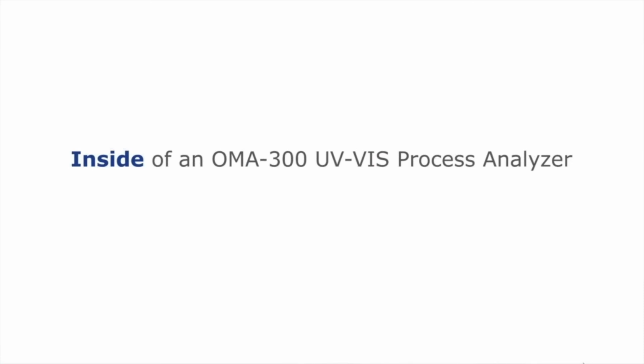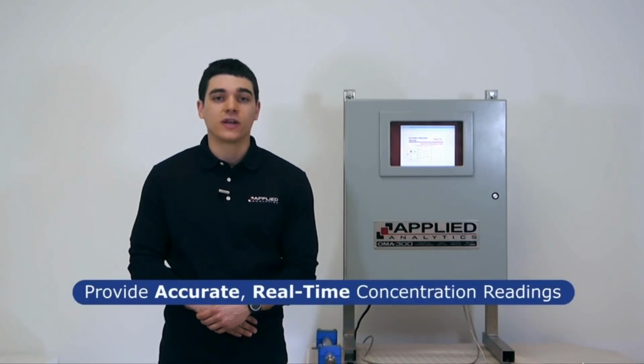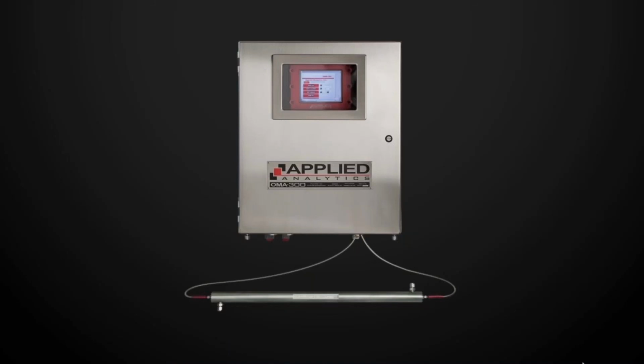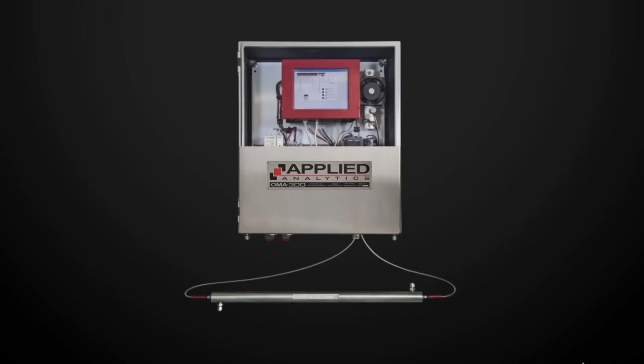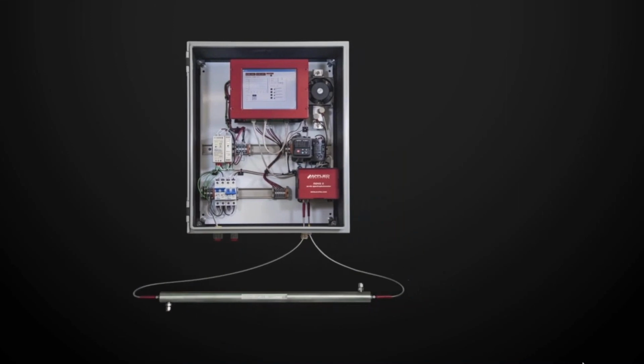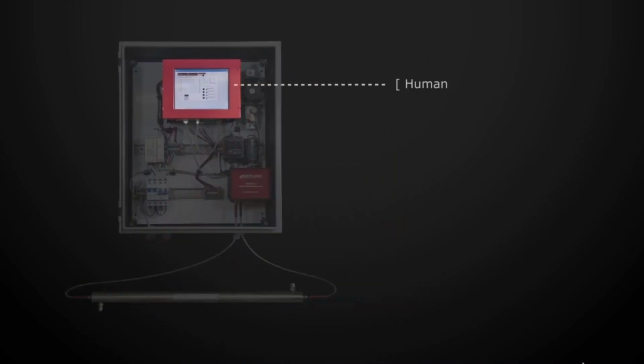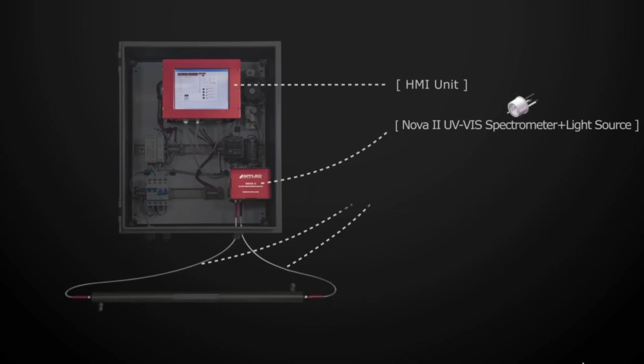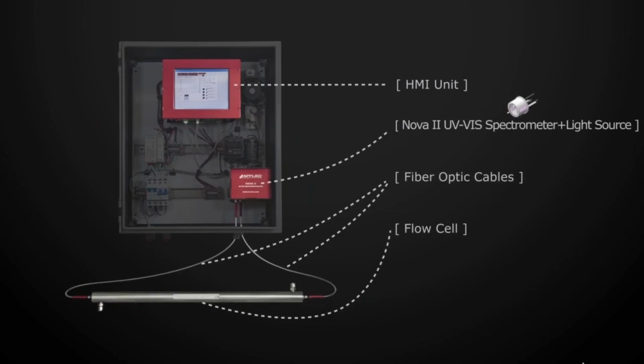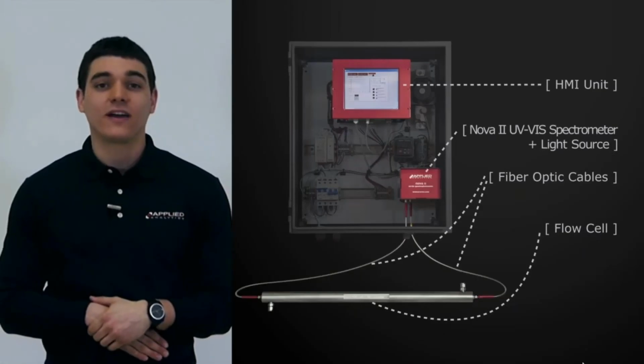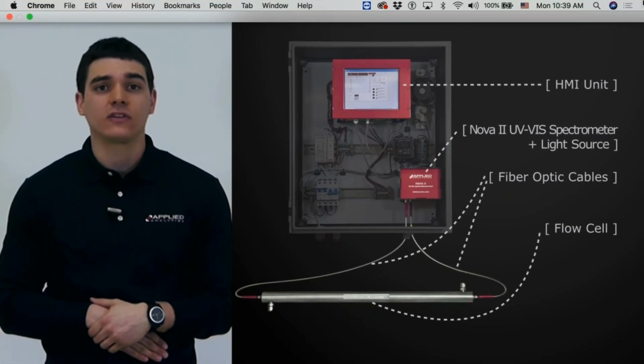Inside of an OMA 300 process analyzer, like this one right here, are several important components that work together to provide accurate, real-time concentration readings of process compounds. Let's take a look. The OMA 300 utilizes several main components to achieve different analytical demands, namely a human interface unit, or HMI unit, the Nova 2 UV-Vis spectrometer, fiber-optic cables, and a flow cell. In real time, these components operate to provide the uniquely characteristic spectrum of each desired process compound, which is then used to accurately determine each component's concentration.